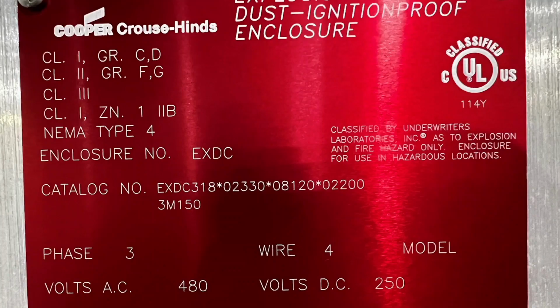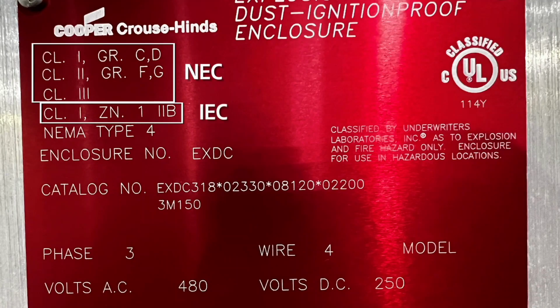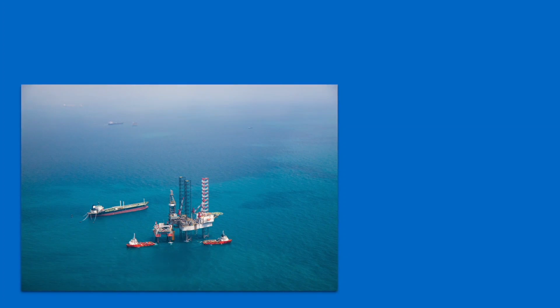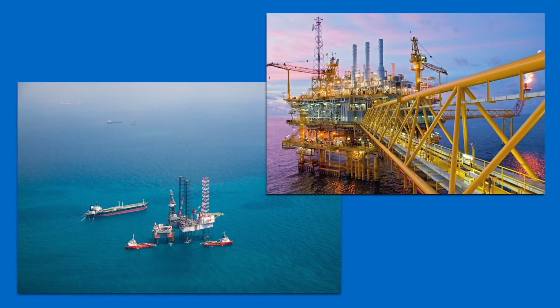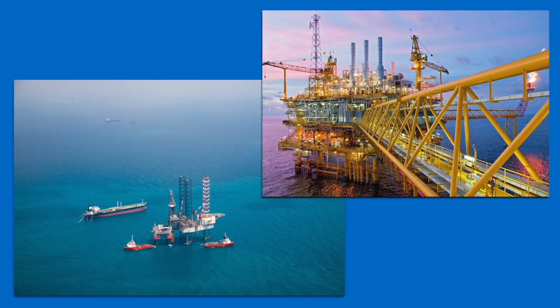In the US, we use NEC Articles 500 to 516. Overall, internationally, we have the IEC 60079 standards. Some equipment has NEC and IEC markings, so the equipment can be adopted better globally, depending on your region. In the Gulf of Mexico, we have some floating assets, like drill ships, that use IEC 60079. The NEC 505 code we use in the US is a variant of the IEC 60079. NEC 505 class and zone seems to be growing more popular than NEC class and division, certainly in the Gulf of Mexico.